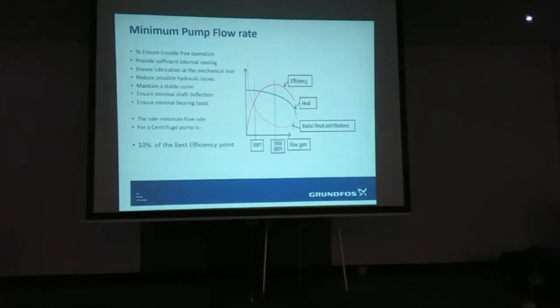Well, you can't go below 10%, because I've said so. Because if it failed, and we found you're running against a closed valve head, and the pump, then it wouldn't necessarily be covered by warranty. And that would be the same with all manufacturers, with the exception of Grundfos, when you use their glandless pumps, which I'll come on to in a minute.